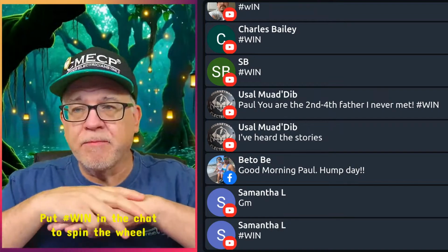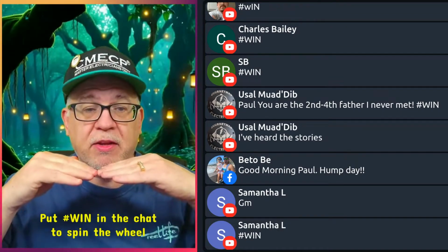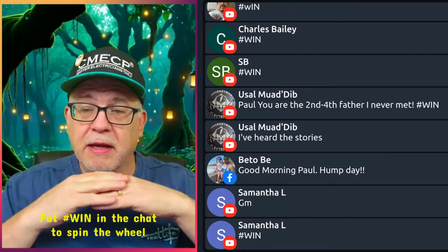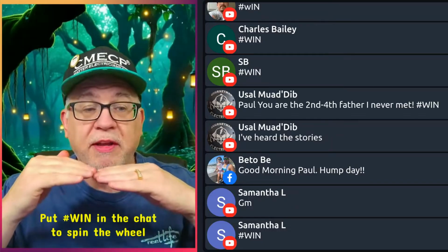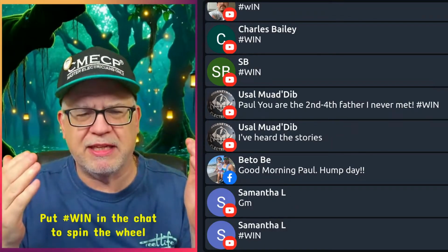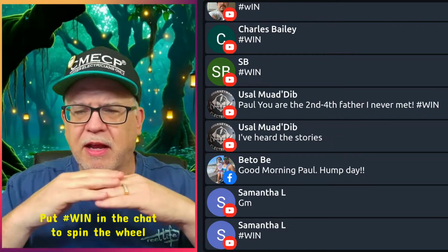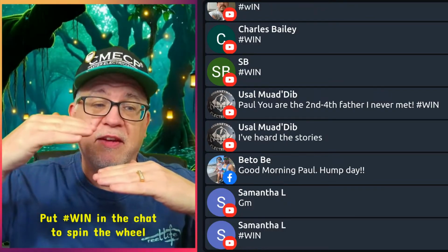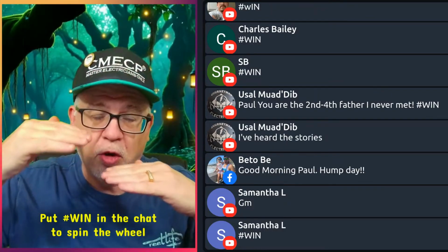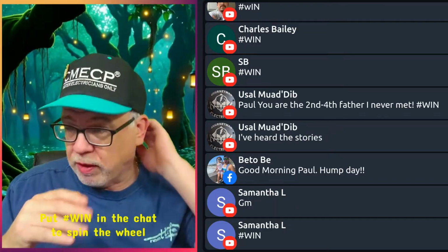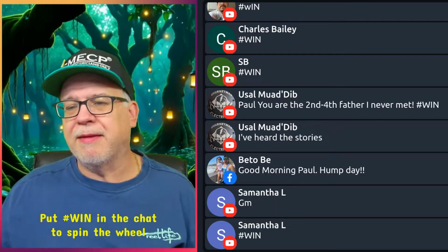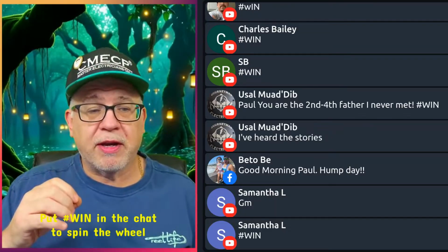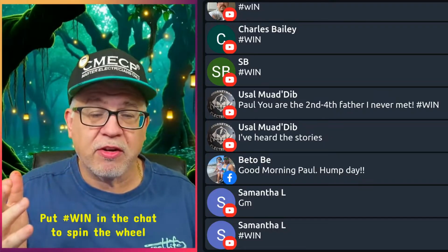In other words, if it's 22 amps and the next standard size was 30, could I put a non-standard 25 amp on that? Absolutely, I could. You get what I'm saying? But the code would allow me to go to the 30 if it was the next standard size over whatever the amp rating is, or whatever the amps are that we need. So again, you do have standard breakers. They do make non-standard, okay?